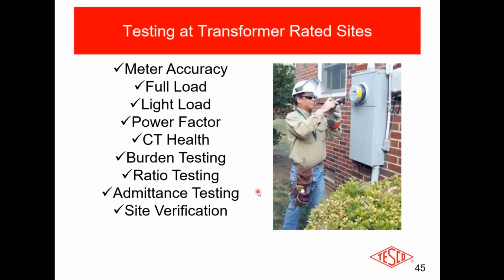An admittance test is a very interesting test in that it's kind of like taking a picture of the meter. And in fact, a lot of utilities do take a picture of your transformer rated sites, especially the larger ones, okay? When they go out there and you're at a refinery or something like that, or one of your big users, and you open up these big boxes, you want to take a picture. Why do you want to take a picture? Because maybe I'm out there this year, but then Joe comes out the year after. Well, if he's got a picture of what I saw last year and he opens up the box and that picture looks exactly the same, he feels a little better that nobody else has been in here monkeying around.